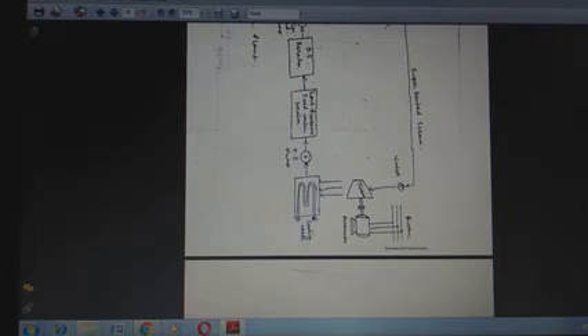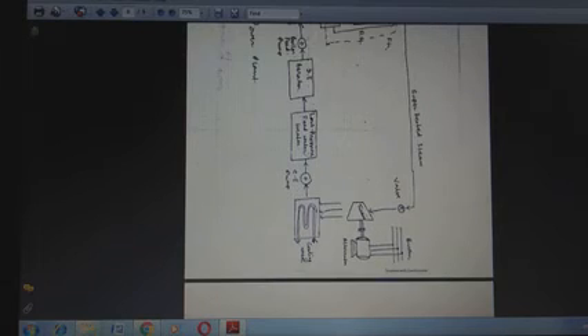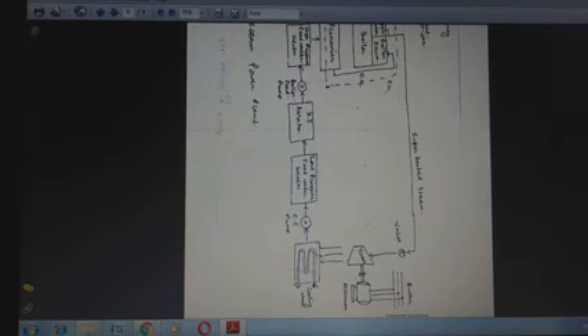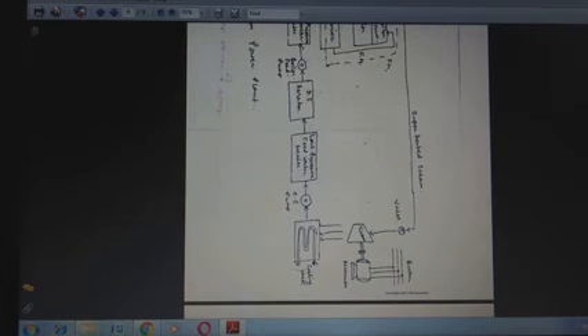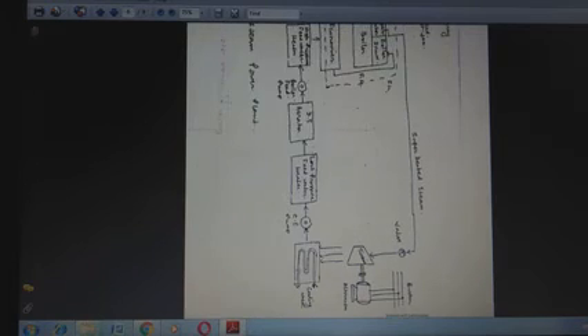So this is the CE pump, that means the condensate extraction pump. The function of this pump is to collect the water with a certain pressure to supply the low pressure feed water heater, deaerator and the high pressure feed water heater. So these plant sections, that is the low pressure feed water heater, deaerator and the high pressure feed water heaters, are basically heaters where the water is heated gradually. And with the low pressure feed water heater, some water treatment plant is also attached. And the water treatment plant is designed with materials like multigraded carbon filter, activated carbon filter, softener, iron removal, etc.